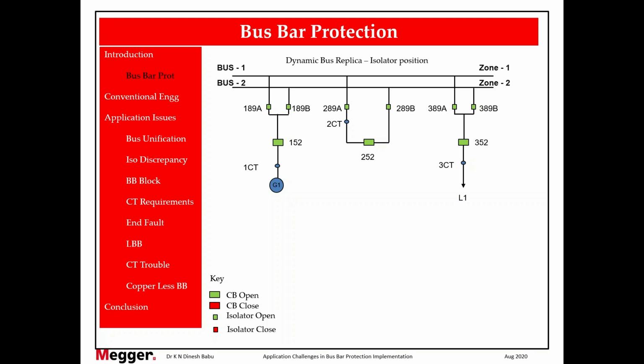So let's see the key. Here we have a small box. This box is called the isolator. I am just representing it in this manner, and the big box is represented as the breaker. Using the ANSI standard, I have given the isolator names. Bay number 1, CT is called 1CT. 89A isolator is called 189A. 89B isolator, which is connected to bus 2, is called 189B. The breaker is called 152. The same terminology repeats for the second bay, third bay. Green color means open, red color means close. The same rule applies for isolators.